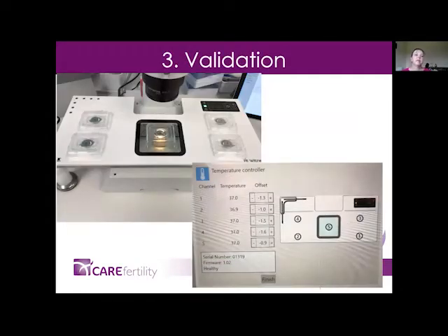This is just a little bit about the validation. Each of the heated plates have 5 discrete areas of heat element, so you can control each of the sections within the work area separately. So we use the thermo buttons for our temperature mapping, and you can see this is one of the workstations that we were validating.